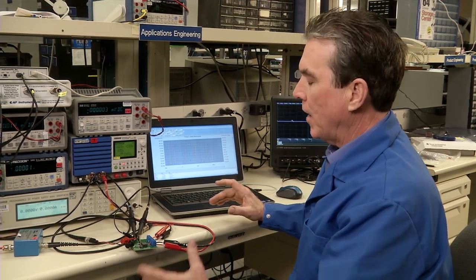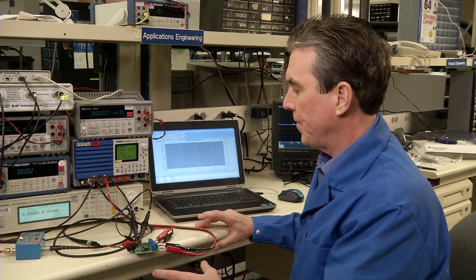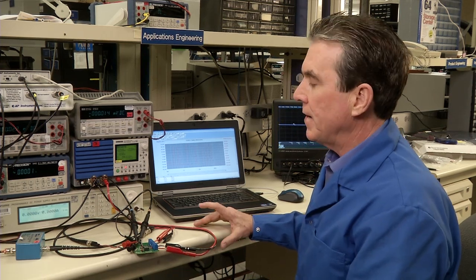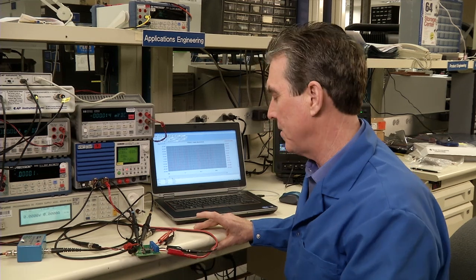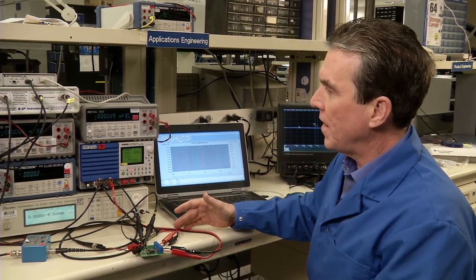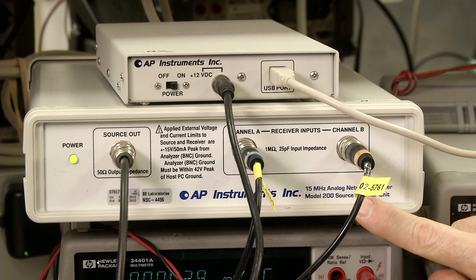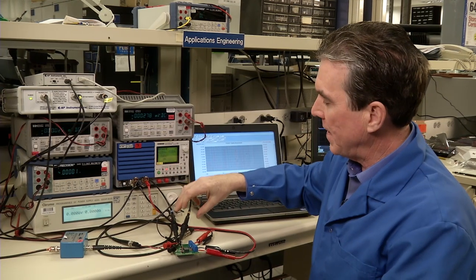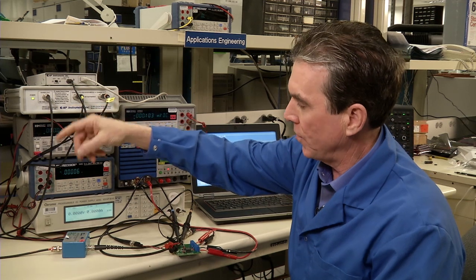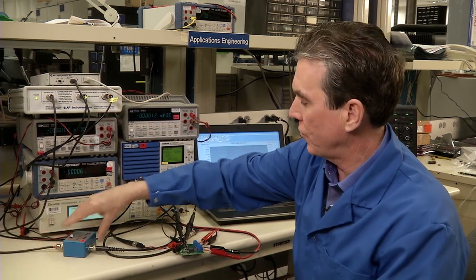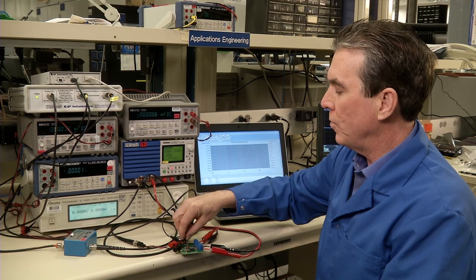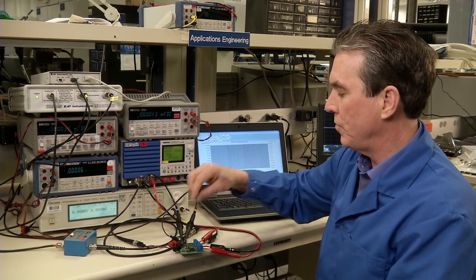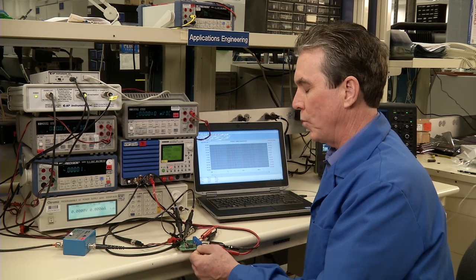Okay, so let's now show you a couple of things. First off, calibration of a network analyzer is very important. The technique for calibrating varies from system to system, so I'm not going to get into that here now, but we're using an AP200, which is up here. Again, probes coming down to the receiver point, and there's a connection to the isolation transformer, which is being injected into two connections that go down to a resistor that's on our evaluation board.